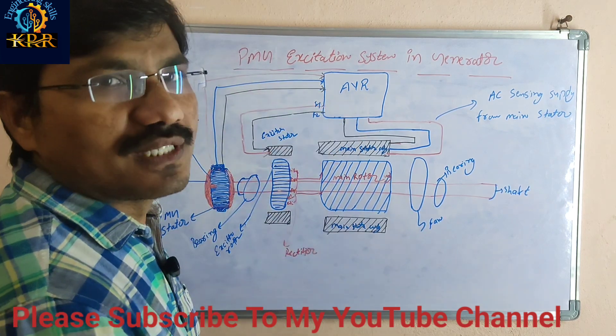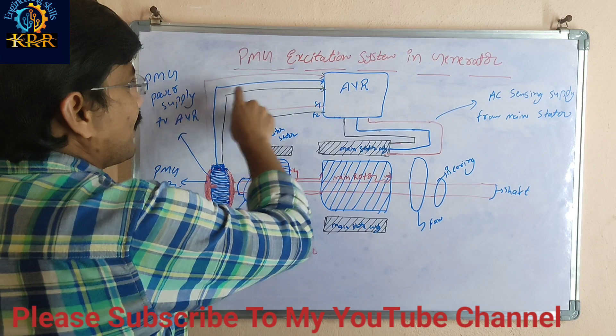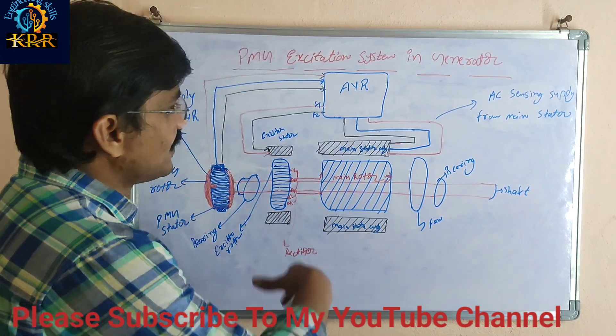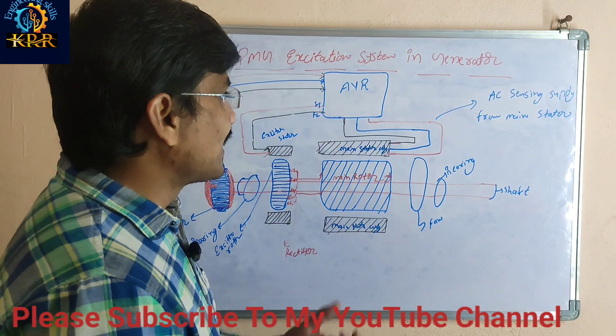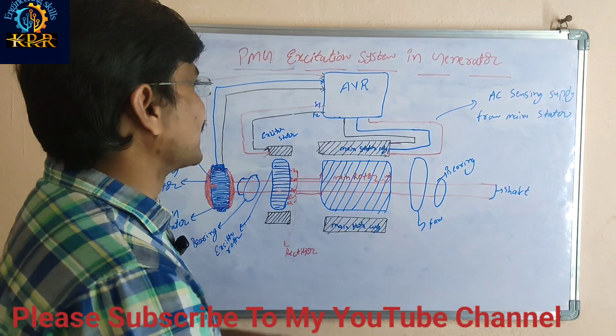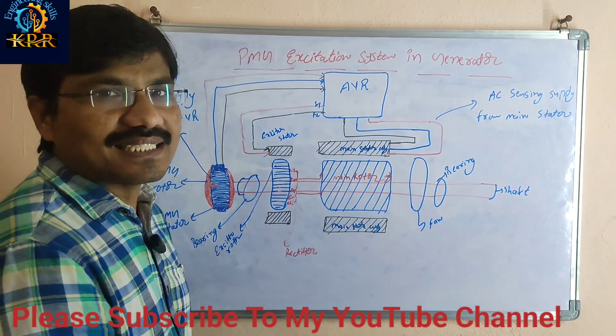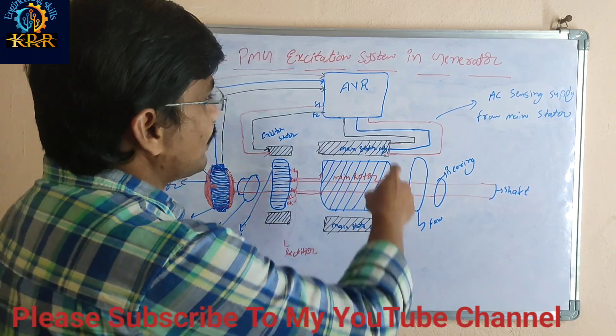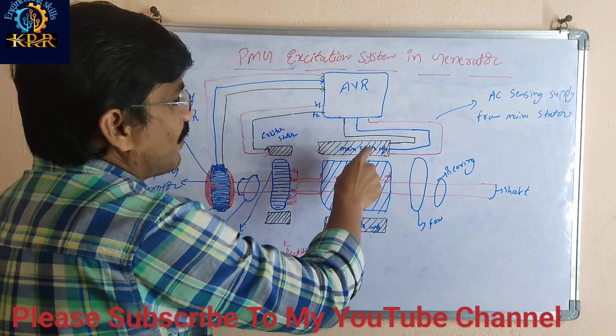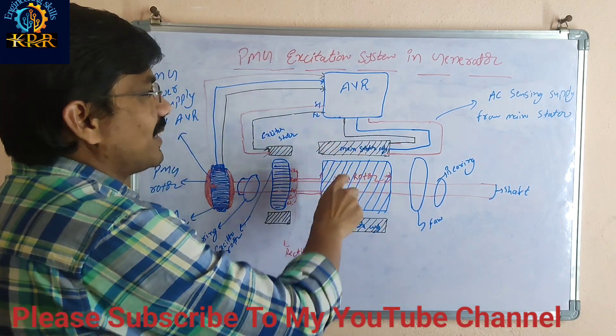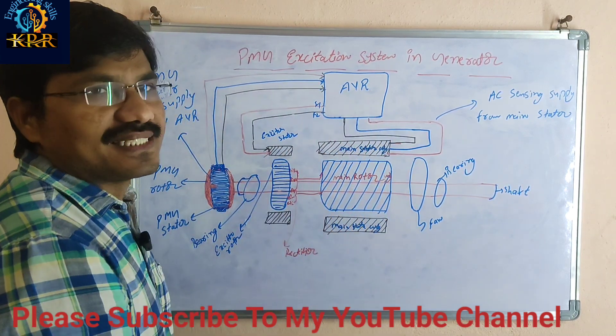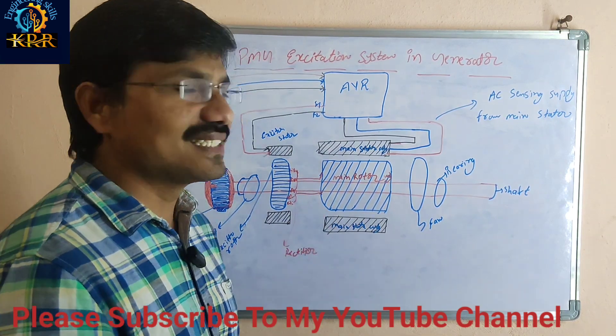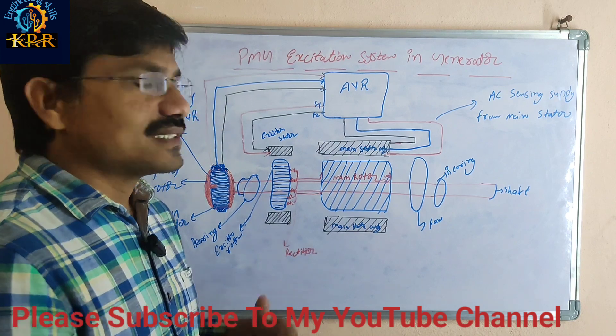The power generated in the PMG stator is supplied to the Automatic Voltage Regulator (AVR). Previously in the self-excitation system, the power supply was taken from the main stator and the sensing was also taken from the main stator. But there are some disadvantages in the self-excitation system.